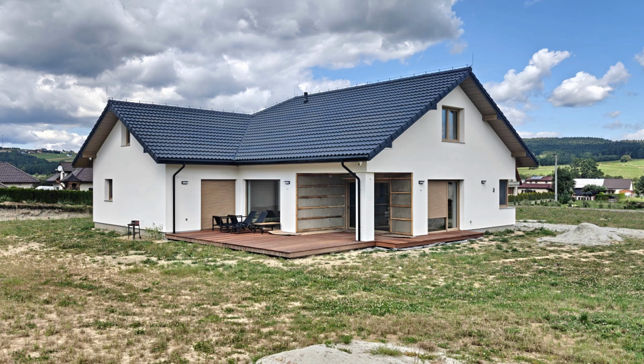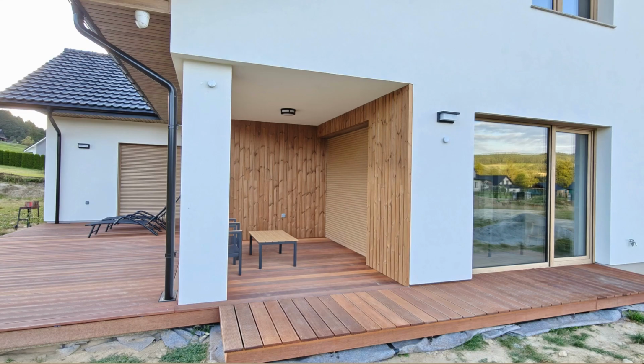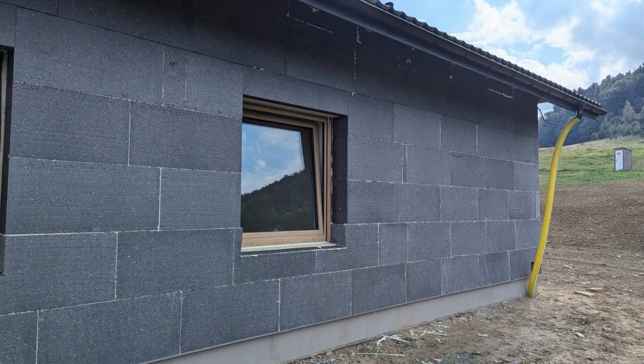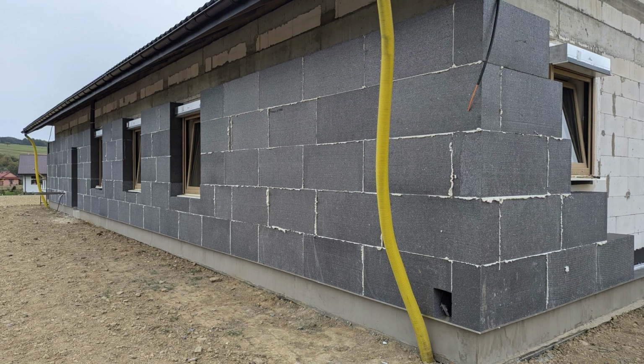The whole setup works very well with automatic blinds, which seem essential for large south-facing windows, and that's the case for me. If the ventilation system and blinds are set to operate automatically inside the building, the temperature never rises above 22 degrees. You just need to be careful not to unnecessarily open windows during heat waves. As the building itself is very well insulated and equipped with the GWC system, the air conditioning unit operated very little, at a low capacity.